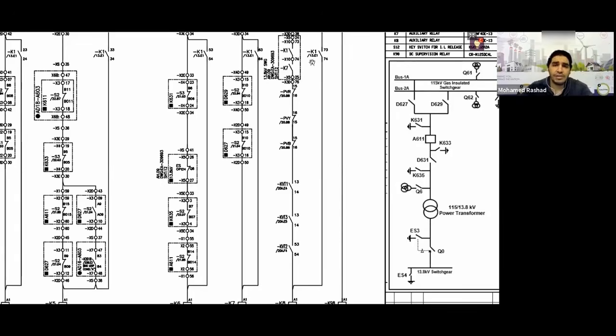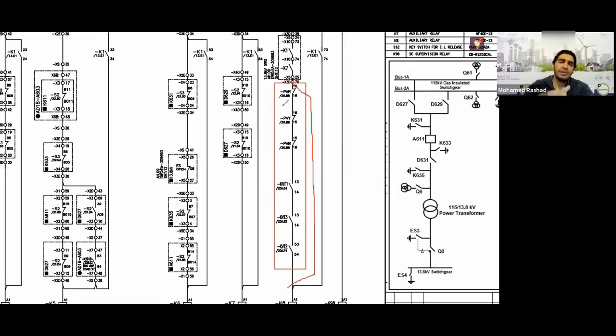Well, if you look at the part I'm going to point out to you now, this is actually an additional part in the drawing, and it's not currently implemented in the station. It should have been drawn or implemented, which is also a mistake by the working engineer. They should have drawn a bypass here, or there is a jumper on it. Actually, I prefer to connect a jumper on it because this part always appears typically in every drawing, but I actually put a jumper on it because it's unnecessary for me since it connects to a transformer.